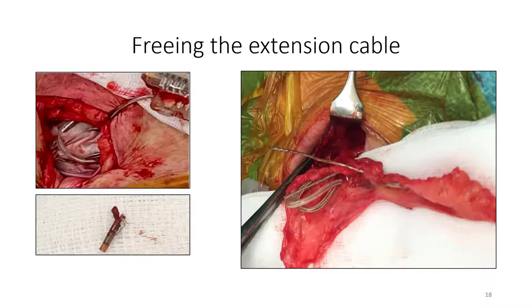Sometimes, if the capsule is not adhering too tightly to the cable, the easiest manner is to remove the cable from the IPG, then find an exposed part of the cable as close as possible to the end and just pull it backwards. At other times, this is not possible.